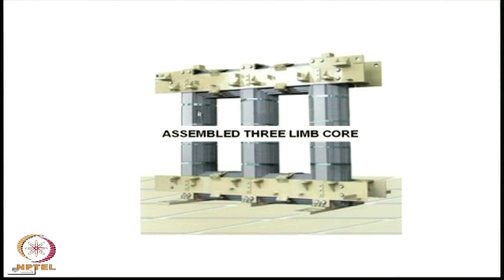Since the flux flows along this direction, the transformer cores are laminated in this way. These cores are made up of long strips of thin steel plate, the material being either hot rolled or cold rolled grain oriented steel. For large transformers, it is usually cold rolled. Since these are made up of steel laminations, it is necessary to bolt them down with clamps. These are the clamping pieces of the core.